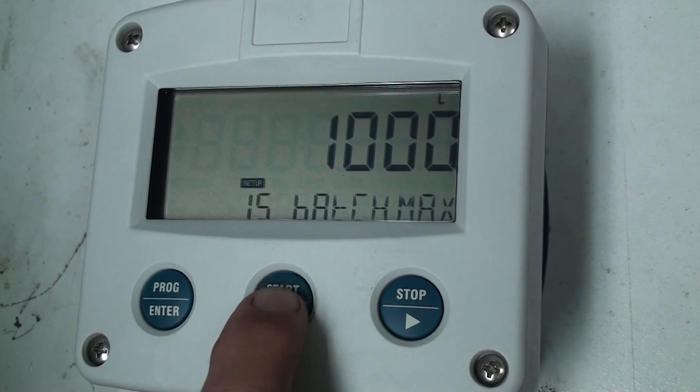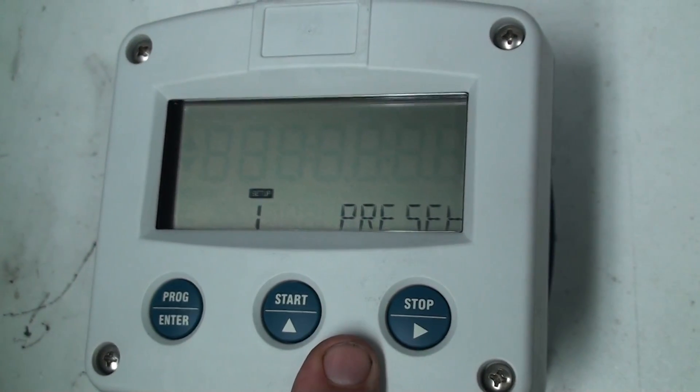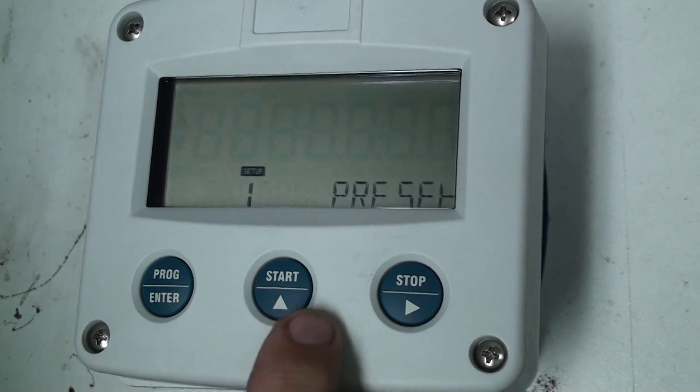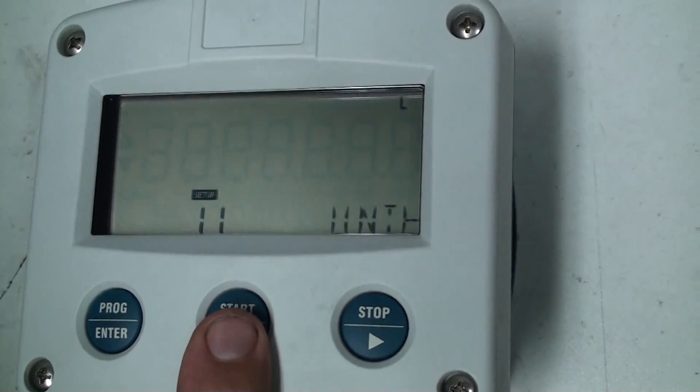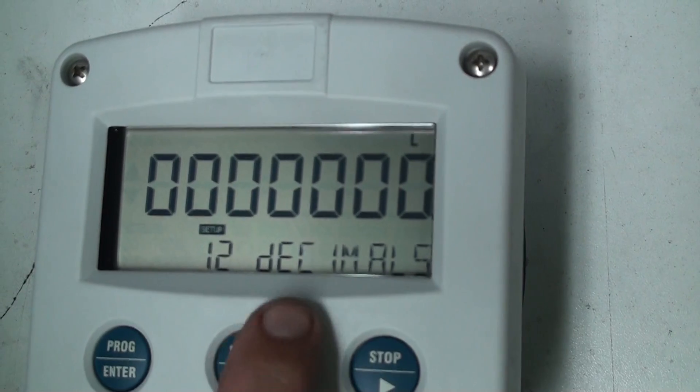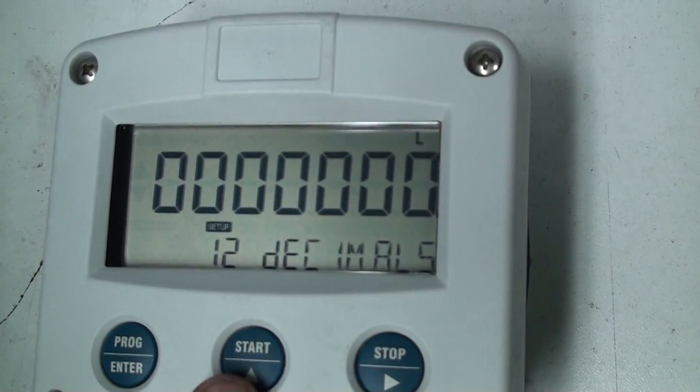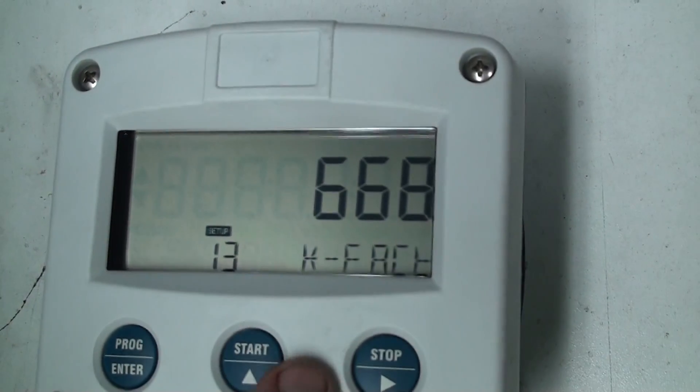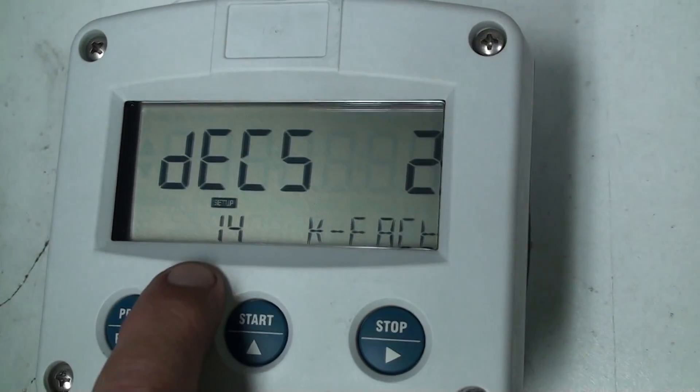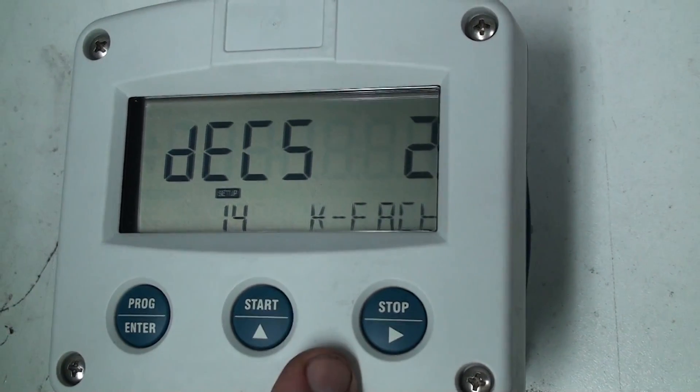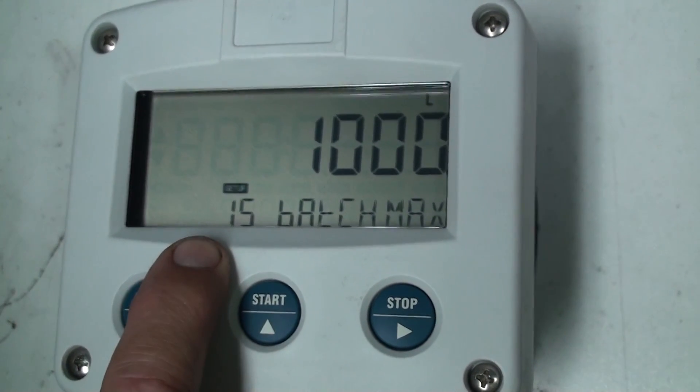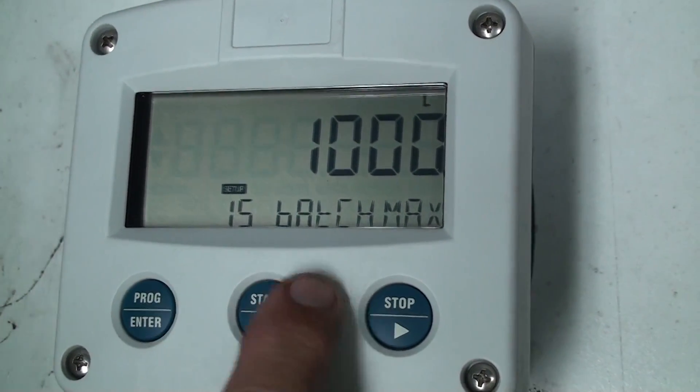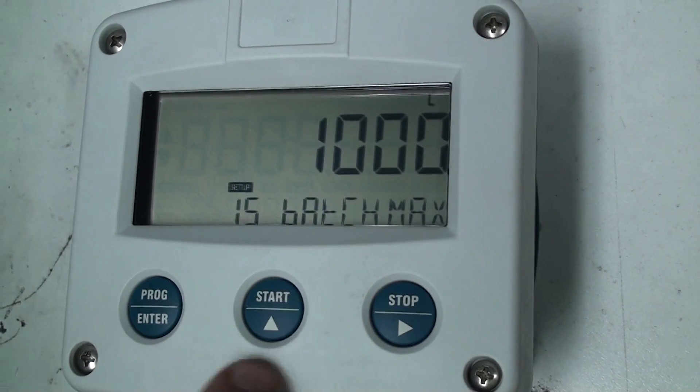We'll go to chapter 1.6 there is no chapter 1.6 so we go back to chapter 1. Now I'll just scroll through chapter 1 to make sure that we've entered everything correct. So 1.1 is for unit in liters, 1.2 is the decimals no decimals, chapter 1.3 is the K factor is 668, chapter 1.4 is 2 decimal points on my 668 which makes it back to 6.68, chapter 1.5 is my batch max set to 1000 that I don't want to batch more than 1000 liters ever.